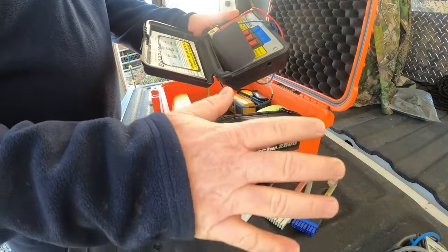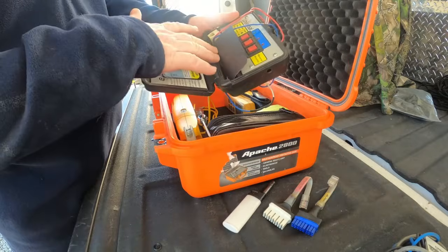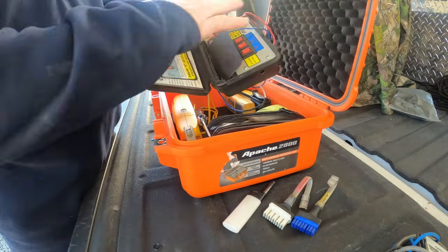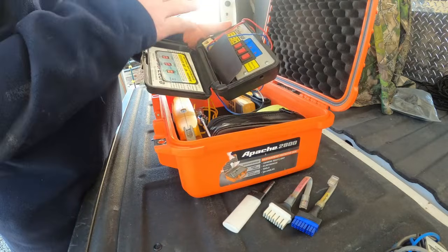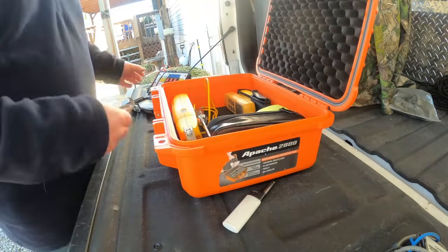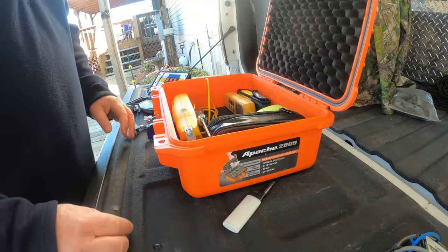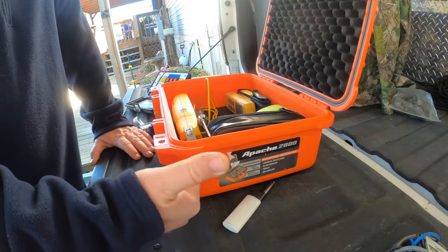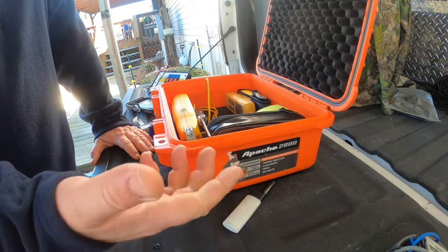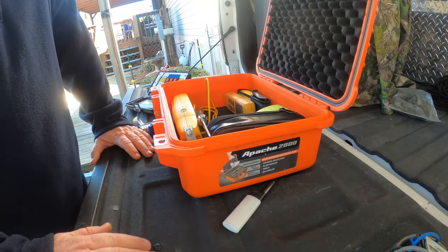If I'm not mistaken, you can get a version of this tester that also has that included as well. So it's one tool that can basically check all your motors, with the exception of your PSCs. And those are pretty common sense motors. Either you got a bad capacitor, that motor's locked and seized, or you got an open winding, one or the other. That's typically what you're going to find on those PSC motors.